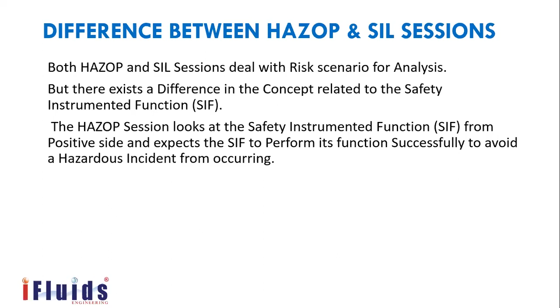Now you can see the HAZOP generally considers the safety instrumented function as one of the protection layers, and it assumes it doesn't fail. But the SIL assessment study, that is the LOPA study, considers the safety instrumented function and its credibility, whether it can fail, and if it fails, what the consequence will be. You can say the next step after HAZOP is LOPA. The HAZOP is qualitative, LOPA is semi-quantitative and QRA is quantitative. So these are the steps. The HAZOP considers all the modes: bypass mode, maintenance mode, startup, shutdown, everything. But LOPA considers only the plant steady-state running: when the demand will occur, and what the credibility of the safety instrumented function is, whether it will function or it will fail.